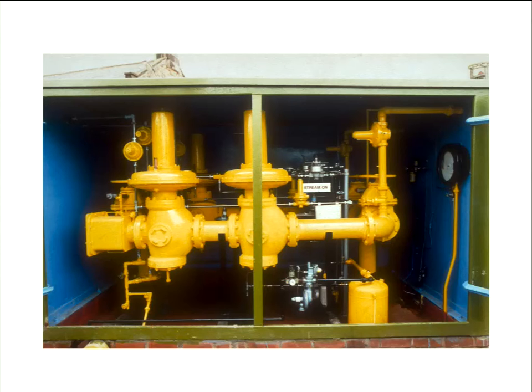As pressure starts to rise, that is fed back onto this side of the diaphragm. So we're talking about a feedback mechanism. It closes the valve a little bit and reduces the flow, and therefore brings the pressure back towards the set point. So you establish an equilibrium that has this valve at the right level of opening for the flow that's needed to maintain the pressure at a particular time.